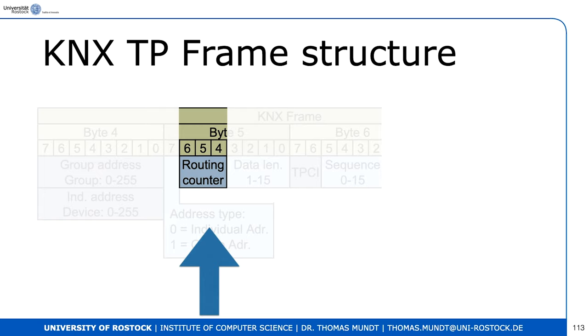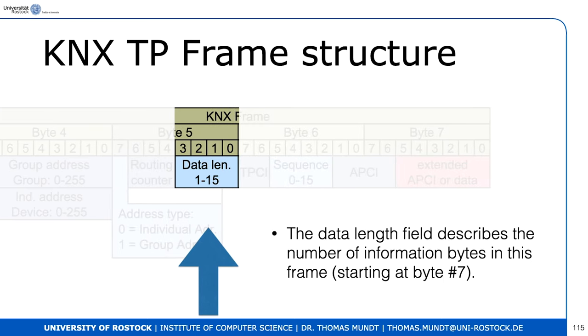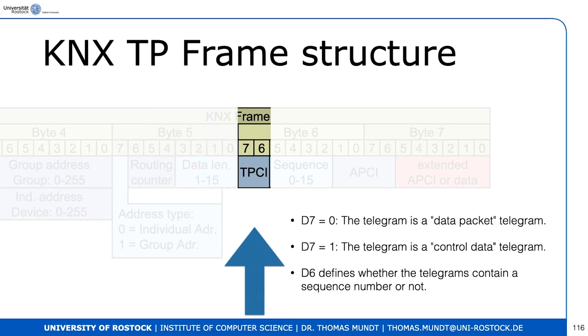We have a routing counter that determines how many hops remain. The counter is decremented every time a frame passes a coupler. At value zero, the frame is removed — it's similar to the time-to-live in IPv4 or hop count in IPv6. Passing a line coupler counts as part of the routing process. The data length field describes the number of information bytes in the frame, starting at byte 7.